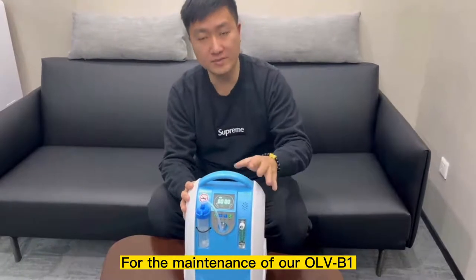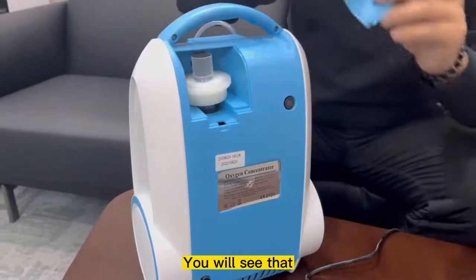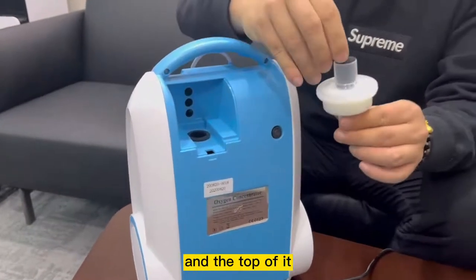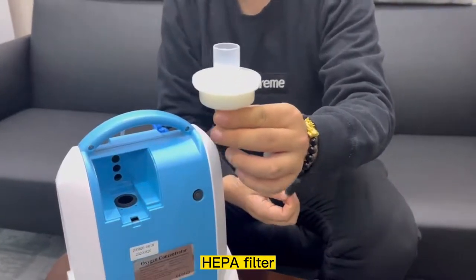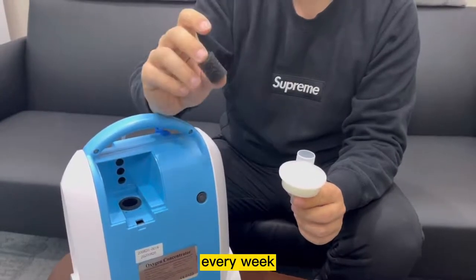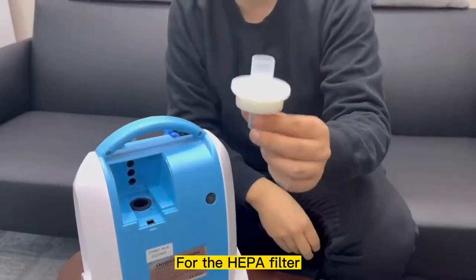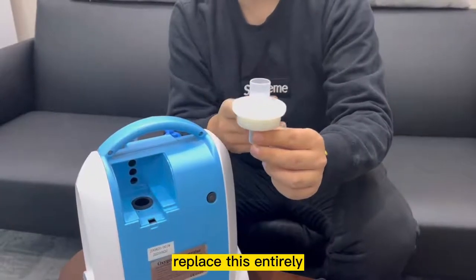For the maintenance of our OLV-B1 model, it's very simple. You can just turn to the back of the machine — of course, turn off the machine first. You'll see that there are two filters inside our machine. At the top is our first filter, and this is our second filter, our high-efficiency HEPA filter. For our first filter, our recommendation is to wash it every week while you're using it. After three to six months of usage, if you feel that it's dirty enough, replace it with a new one. For the HEPA filter, this is not washable — our recommendation is after around 3,000 hours of usage, replace this entirely.